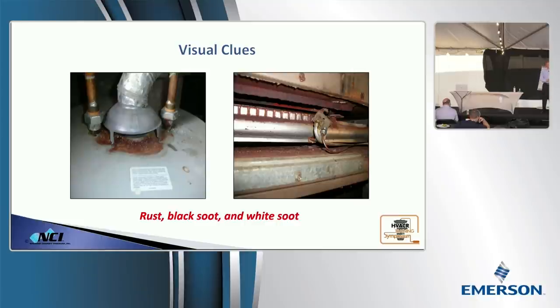How many times have you guys ever seen the rust donut around a water heater draft hood? All the time. That's not a good thing, Mark. It's normal, but it's not a good thing. What's causing that? Intense heat? It's not drafting properly. It's flue gas condensing. John Ellis said flue gas condensing. Flue gas has a pH of about 3.8.